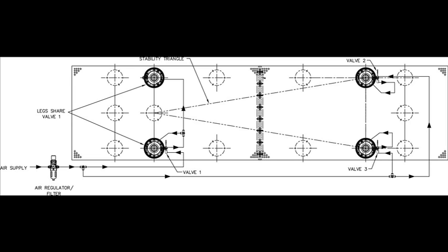The two isolators on the left share the output of valve one, while the isolators on the right are controlled by individual valves two and three. This three-valve configuration is standard regardless of how many legs are supporting the system. Including more than three valves in any system can cause instability and make it very difficult to properly level the table system.